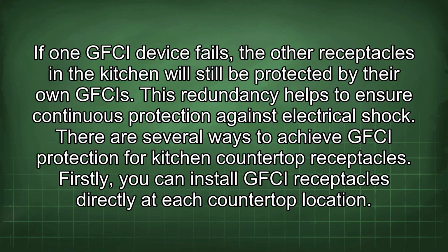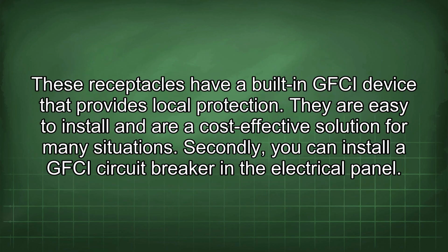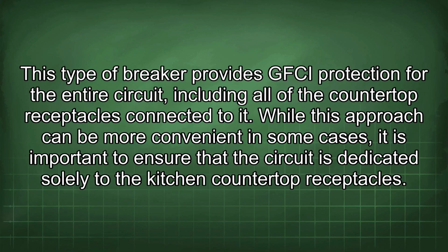There are several ways to achieve GFCI protection for kitchen countertop receptacles. Firstly, you can install GFCI receptacles directly at each countertop location. These receptacles have a built-in GFCI device that provides local protection. They are easy to install and are a cost-effective solution for many situations. Secondly, you can install a GFCI circuit breaker in the electrical panel. This type of breaker provides GFCI protection for the entire circuit, including all of the countertop receptacles connected to it.